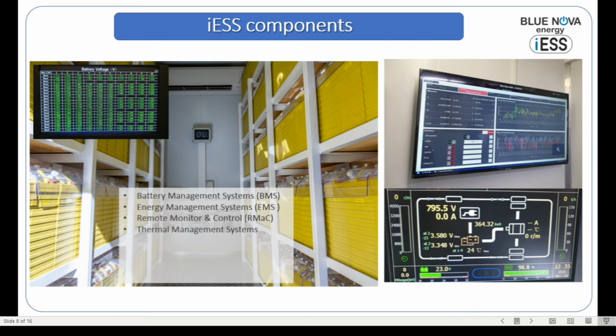It comes with a built-in thermal management system to make sure that all the components are running under optimal environmental and climatic conditions. We have an internal electrical distribution system that couples the AC component with the DC component in the two different chambers in the unit, but also allows for the electrical interface to the AC distribution board, which is outside the system.